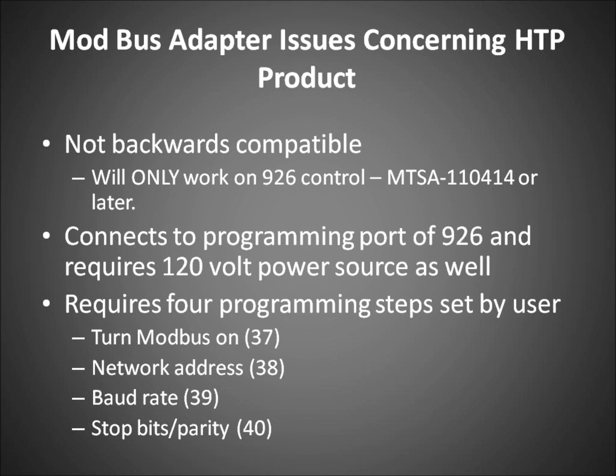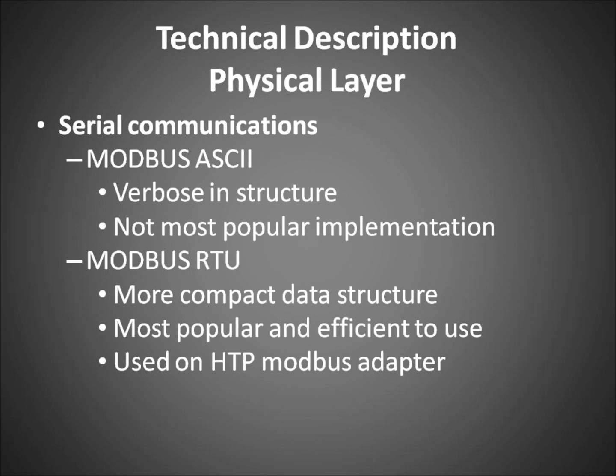Connections to the programming port of the 926 require a 120-volt power source as well. Some of the basic requirements for programming: there are basically 4 steps. Within the appliance, when you're programming your parameters, you need to turn the ModBus on, function 37; function 38, the network address; function 39, the baud rate. There are 2 different baud rates, and it'll be selected by the person implementing the building management system, so we'll know what baud rate we should have. And then the stop bits and parity, which is function 40. So just like changing an outdoor reset, these 4 parameters need to be adjusted within the appliance programming function in order to activate the ModBus adapter to the building management system.